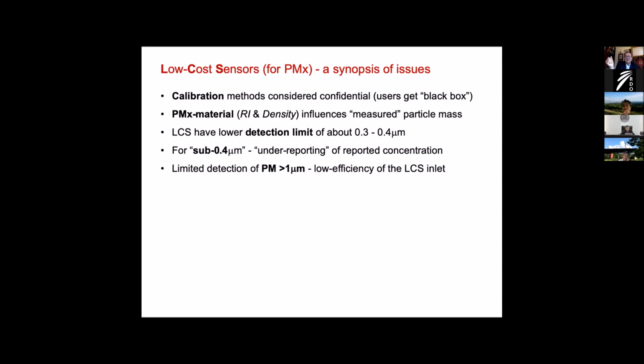Then there's the question of the lower detection limit of the sensitivity. Usually low-cost sensors stop measuring between 0.3 and 0.4 micrometers. Well, that means if we measure PM2.5 and we are losing the particles at the low end, you remember from one of my first slides, the small particles have little mass. So one could think, well, if I cannot count smaller than 0.3, it doesn't matter.